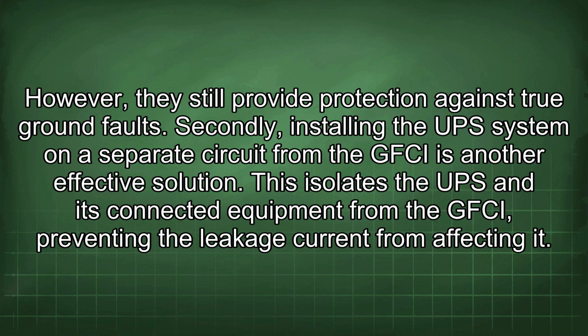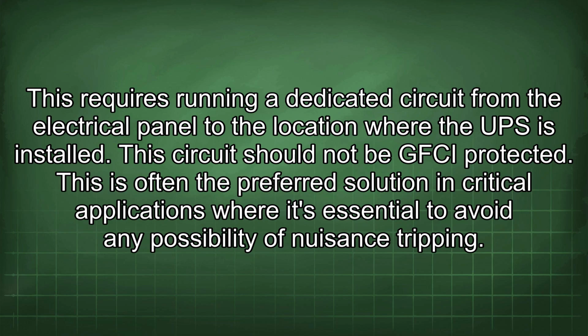Secondly, installing the UPS system on a separate circuit from the GFCI is another effective solution. This isolates the UPS and its connected equipment from the GFCI, preventing the leakage current from affecting it. This requires running a dedicated circuit from the electrical panel to the location where the UPS is installed. This circuit should not be GFCI protected. This is often the preferred solution in critical applications where it's essential to avoid any possibility of nuisance tripping.